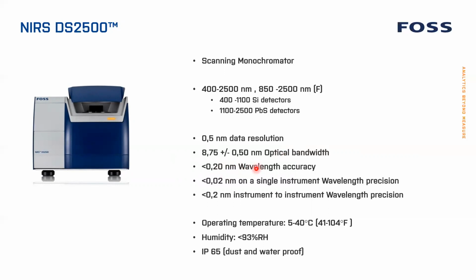And then we have the wavelength accuracy and precision on one single instrument and precision from instrument to instrument. These numbers are important for us when we develop instruments, and they are important when we develop calibrations because they go together. So now saying that calibrations can be moved from one instrument to another instrument, it's important that we stay within these specifications to make that possible. And it also has some influence sometimes when we develop calibrations that the calibration itself needs to be able to work within this variation.